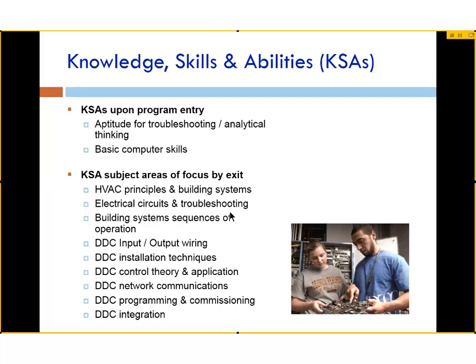Another key area is building systems sequences of operation. Buildings today are more complex than ever. You have not just HVAC systems to control, but daylighting, reducing lighting levels in spaces based on ambient light from outside, which USGBC encourages for energy savings, adding to the sequences of operation. You're also seeing more access controls, lighting controls, security controls, and card access running through the building automation system these days.